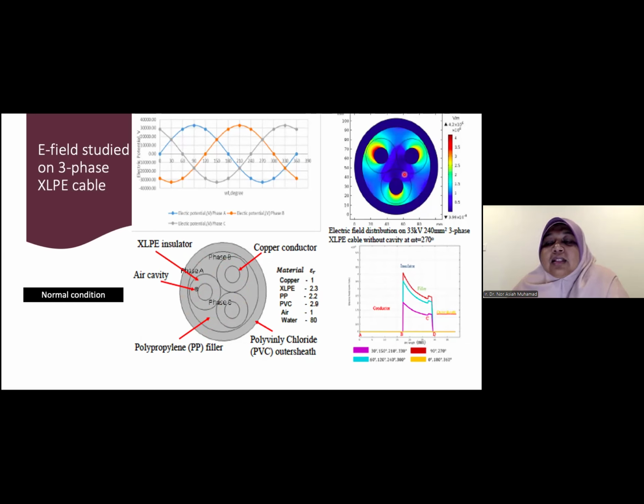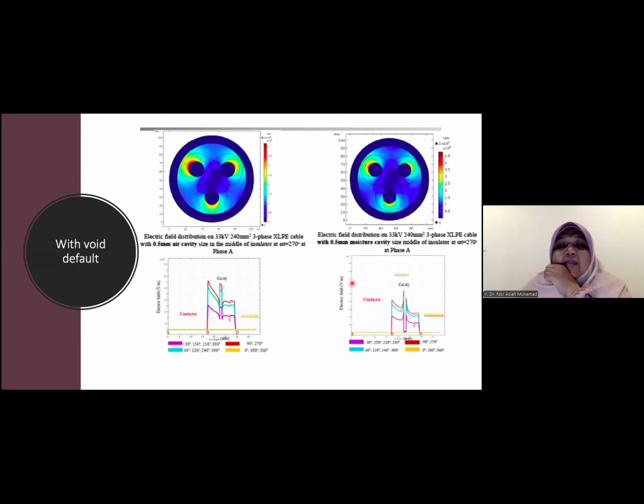So in the example here we have the E-field with no cavity. We will know that with this design, the maximum E-field is at a certain value. Then when there is a cavity inside, a void, the E-field changes. So our insulation material needs to be designed so that it can at least withstand the cavity size. This is one of the steps to design the best insulating material. Selecting the insulating material, we will try different materials and see how high the E-field is with the cavity.